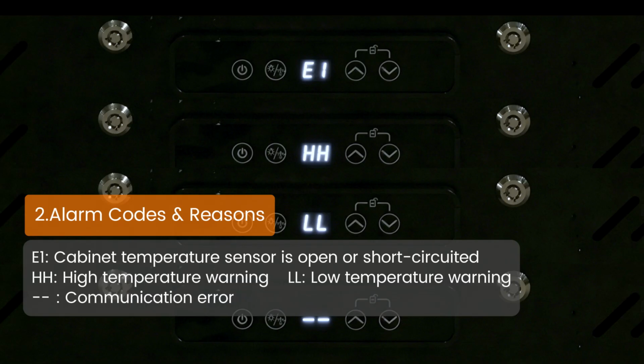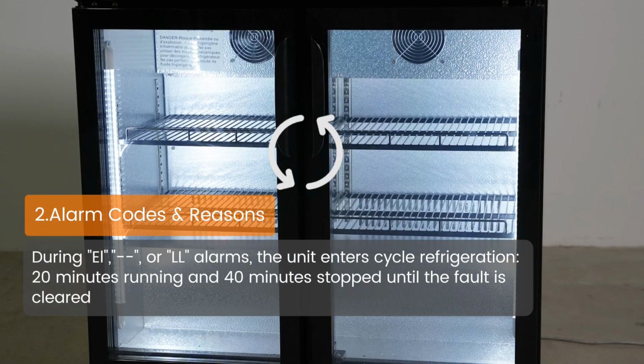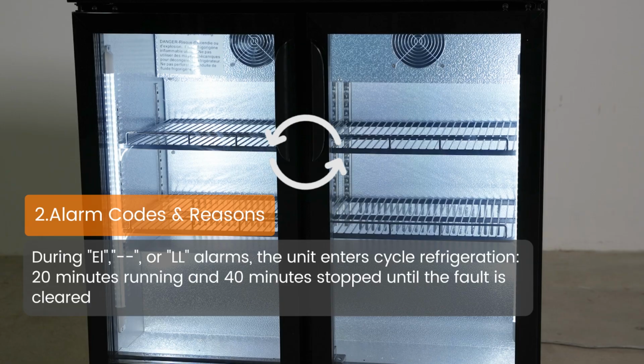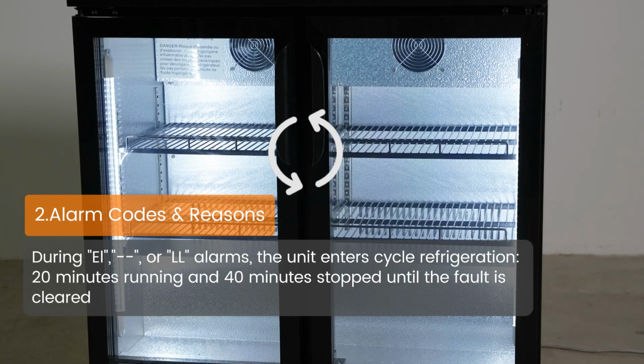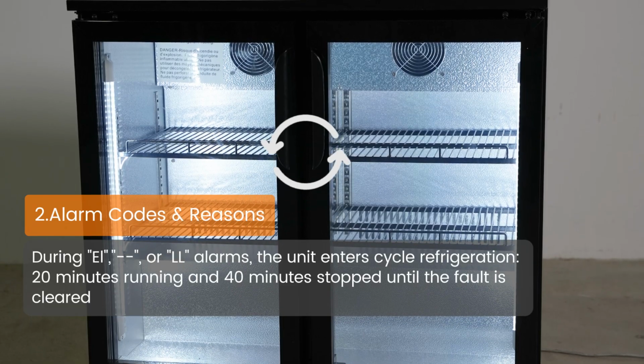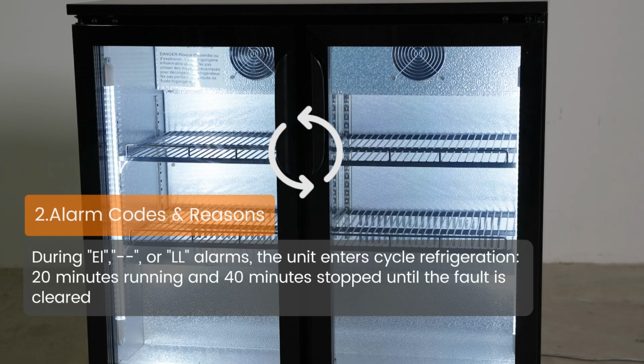2. Alarm codes and reasons. Cabinet temperature sensor is open or short-circuited. HH: high temperature warning. LL: low temperature warning. Communication error. During "E1", "--", or "LL" alarms, the unit enters cycle refrigeration: 20 minutes running and 40 minutes stopped until the fault is cleared.